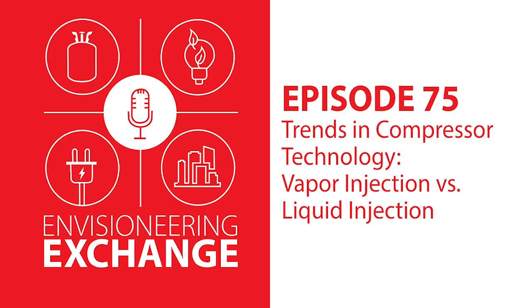And it's really about finding first the compressor that can balance all those different points as far as the unit design goes. That's the first step, right? To pick the compressor that meets the unit capacity. That's the heart of the system, basically, right? And you mentioned that by doing the injection, in essence, that compressor is going to be able to do more capacity than it would have been without it, right? I think that's one way you get the efficiency. You can take a 4-ton compressor and maybe get 4.5 tons with injection. So you're using a smaller motor to get larger capacity, which obviously helps your COP.